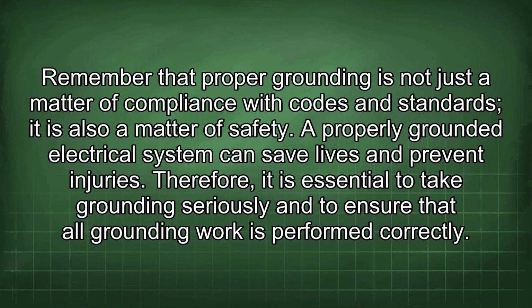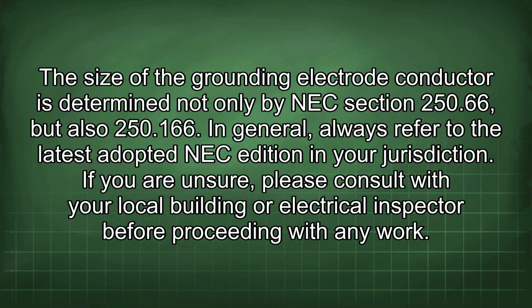Remember that proper grounding is not just a matter of compliance with codes and standards, it is also a matter of safety. A properly grounded electrical system can save lives and prevent injuries. Therefore, it is essential to take grounding seriously and to ensure that all grounding work is performed correctly. The size of the grounding electrode conductor is determined not only by NEC section 250.66, but also 250.166. In general, always refer to the latest adopted NEC edition in your jurisdiction. If you are unsure, please consult with your local building or electrical inspector before proceeding with any work.